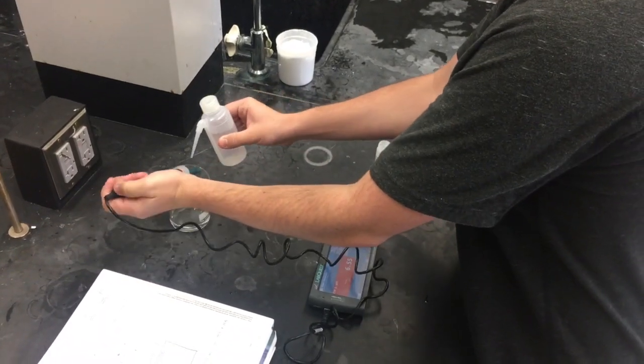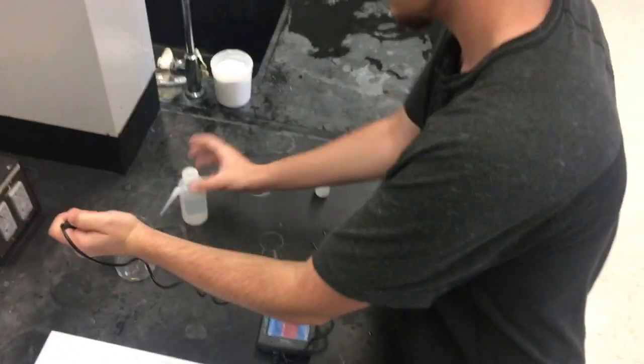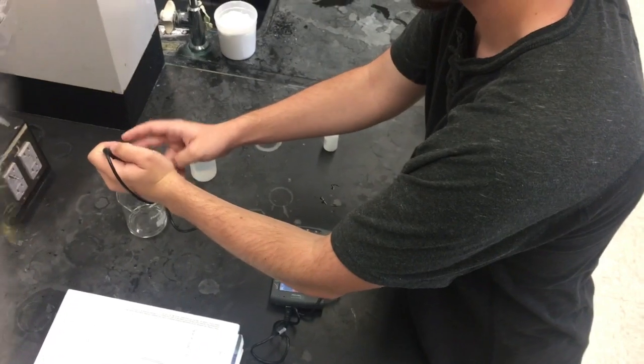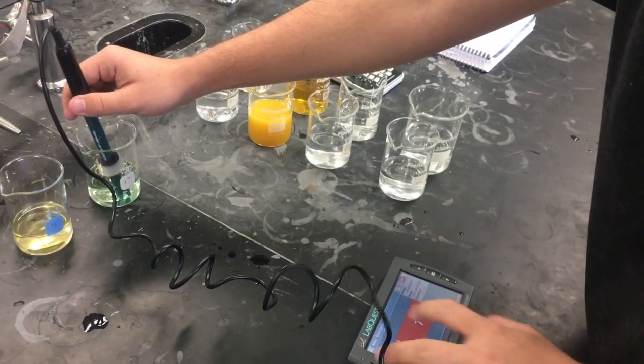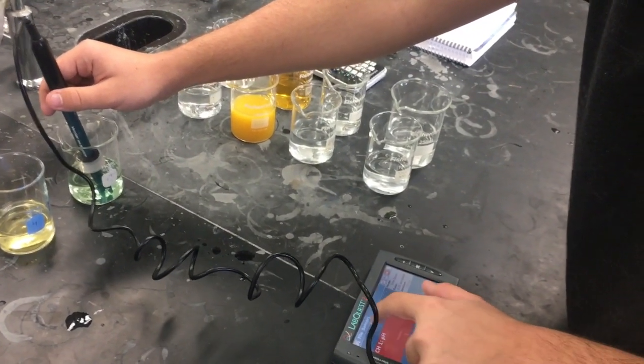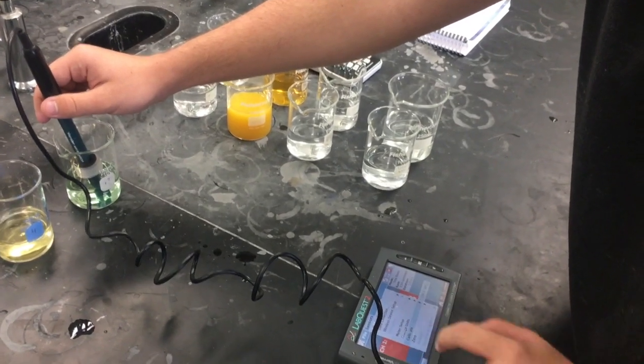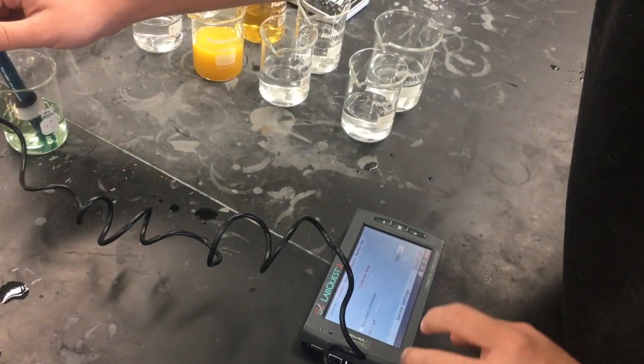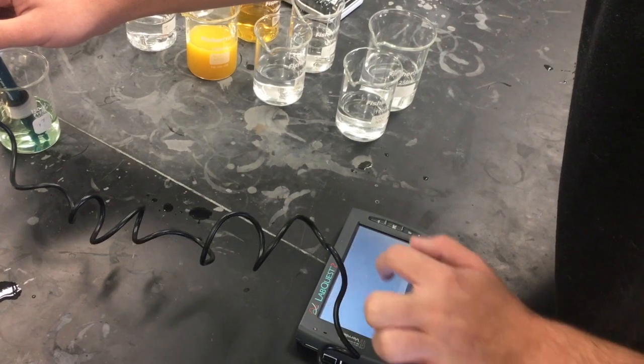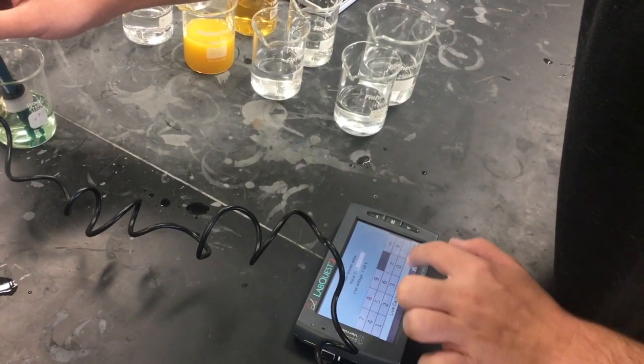Before calibrating the pH meter, my colleague here, Logan, washes it off with distilled water. We use a 2-point calibration method to calibrate the pH meter. First, after cleaning the meter, we put it in a pH 7 buffer solution which has a green tint to it.